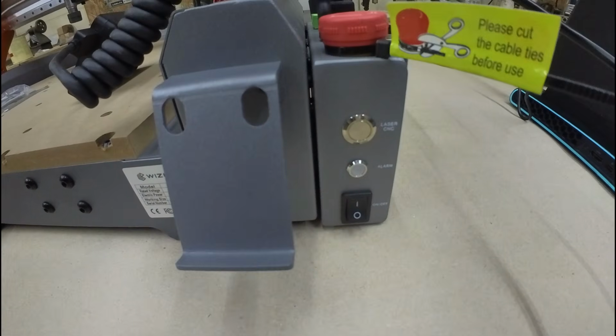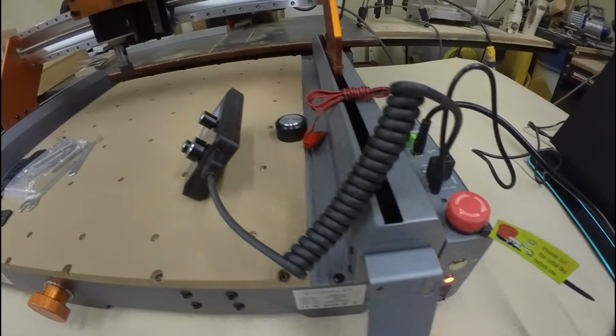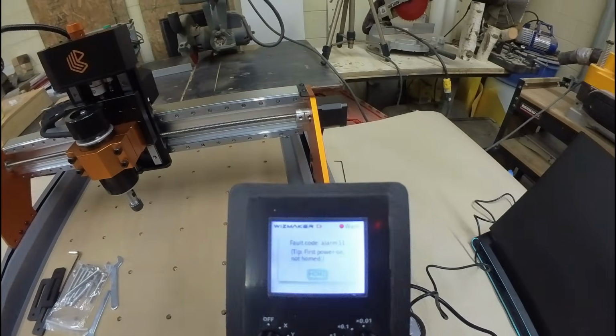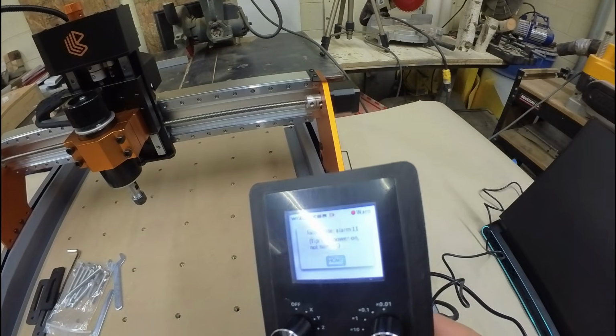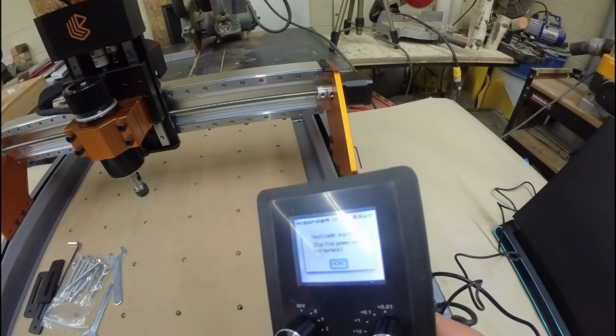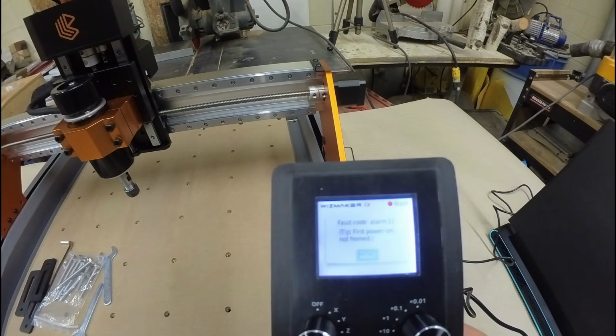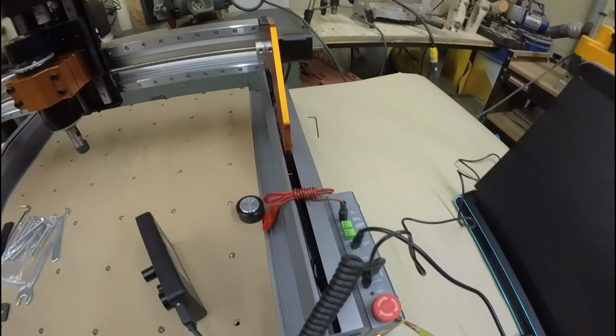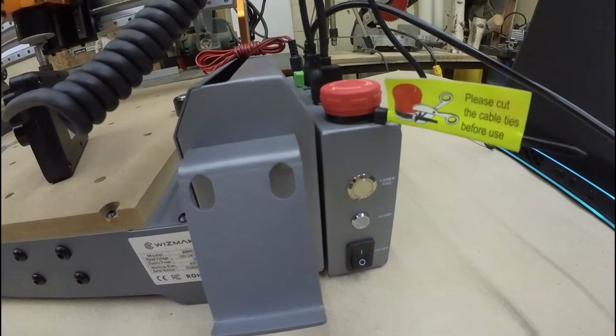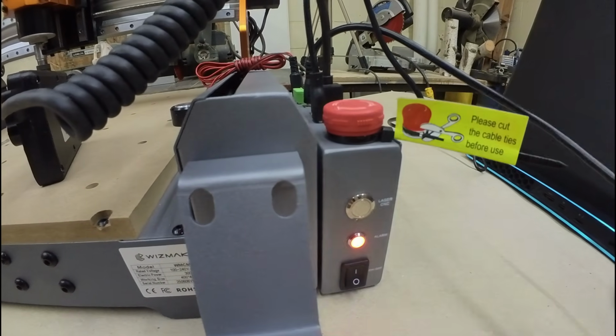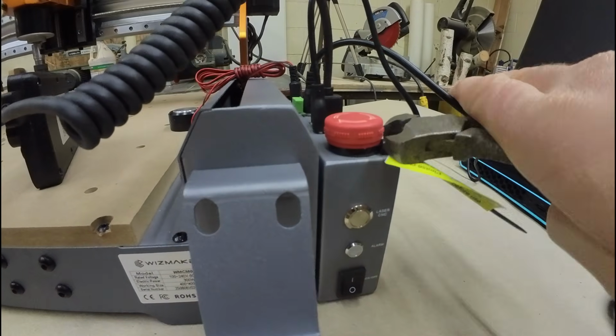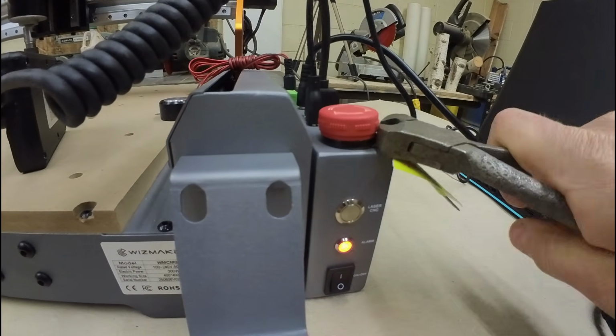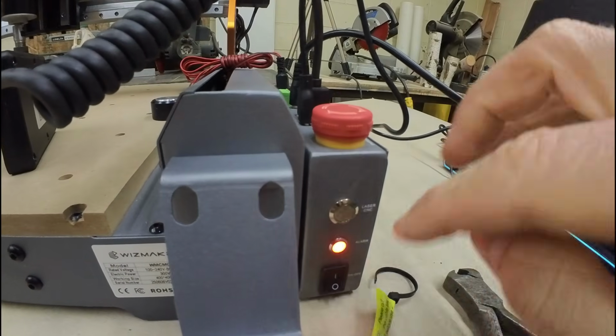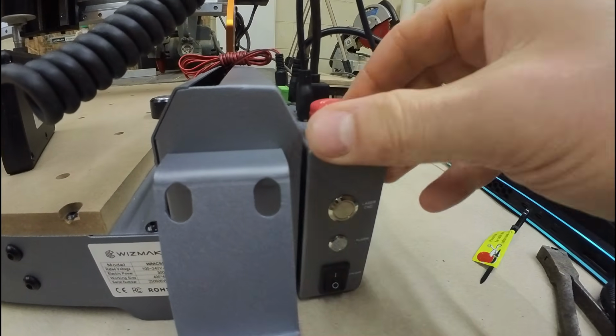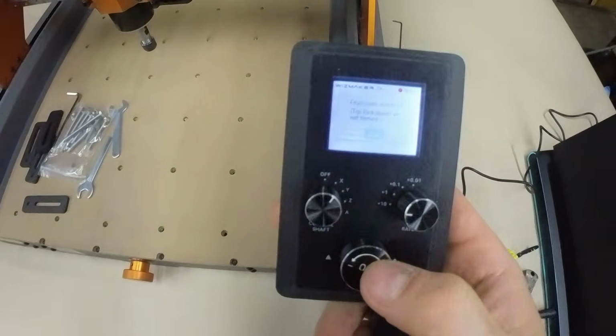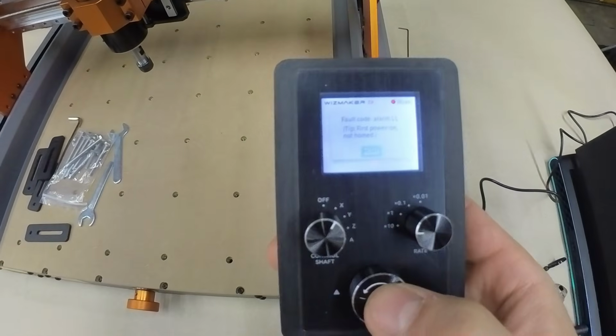Alright, I just turned this on, and this alarm started going off, so I connected the control panel. It has an error that immediately came on, and it just says that this is the first power on, so we need to go through its first homing before we do anything. We'll cut this tie, the emergency... just in case. Alright, push OK.